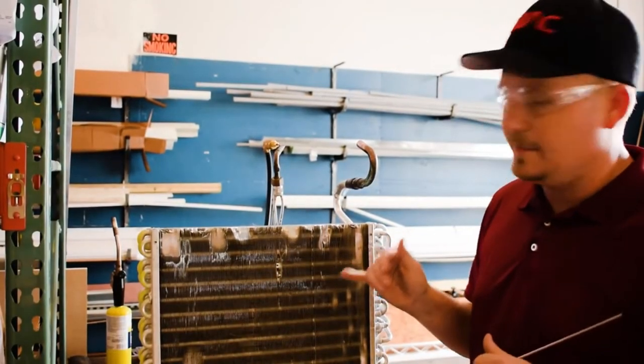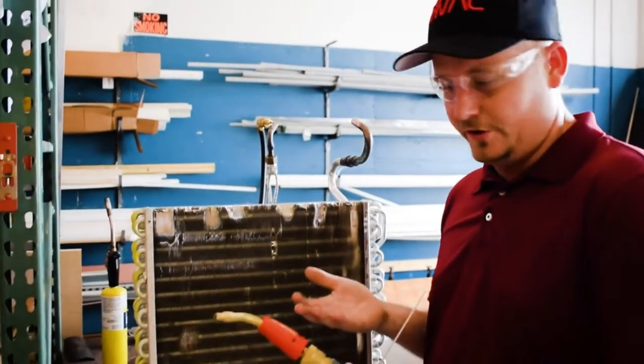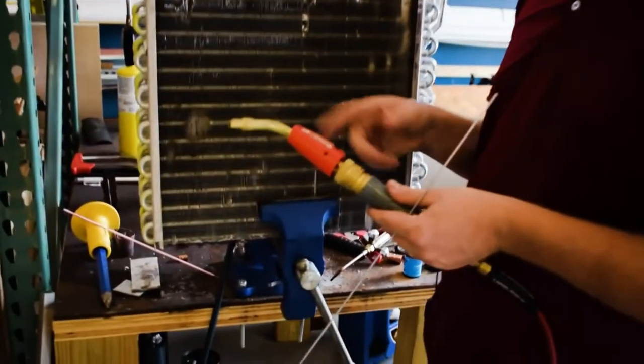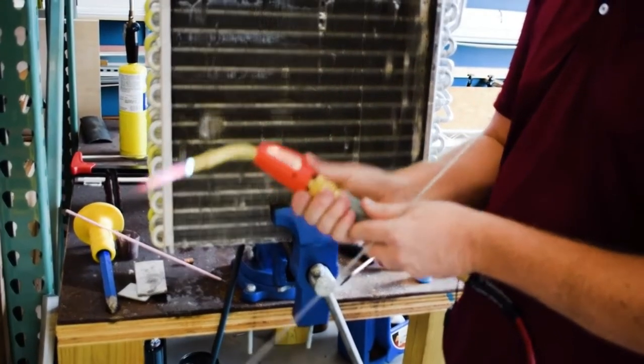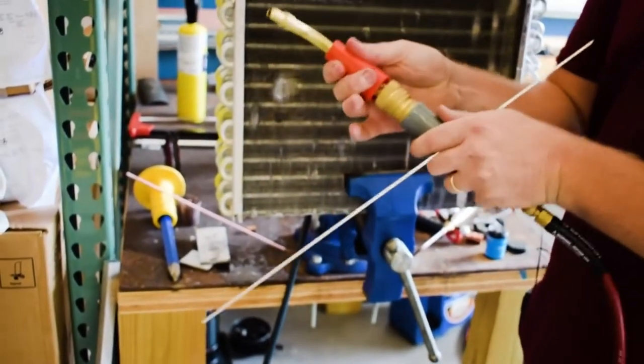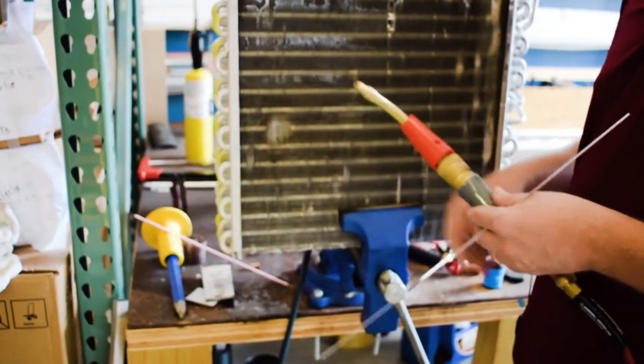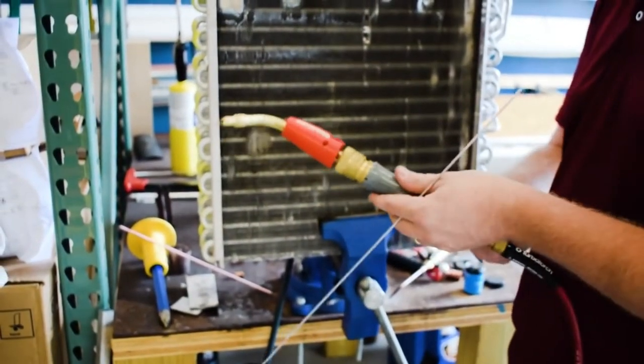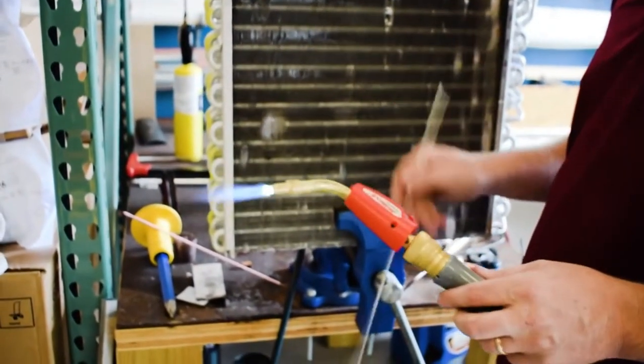A lot of guys have asked about this. I really like both oxyacetylene and air acetylene. I've used oxyacetylene my whole career. Air acetylene is great because it's so simple. You don't have to think about it when you light it. One thing to keep in mind, and this is a mistake guys make, you want to make sure this is really snapped in. You don't want to modulate the heat. You modulate the heat by choosing the tip more than anything. I see guys trying to modulate the heat and you can burn back down into the tip, which becomes dangerous. Just make sure it's in place, open it up, and now we're cooking with gas.